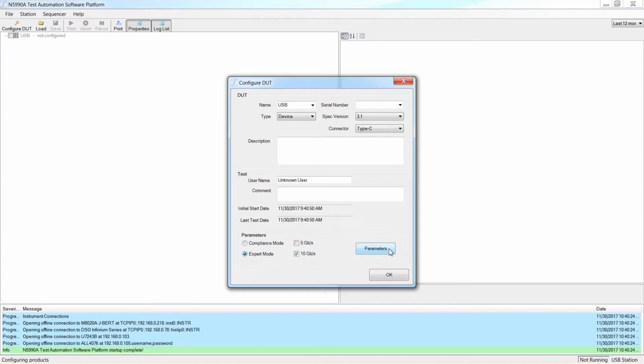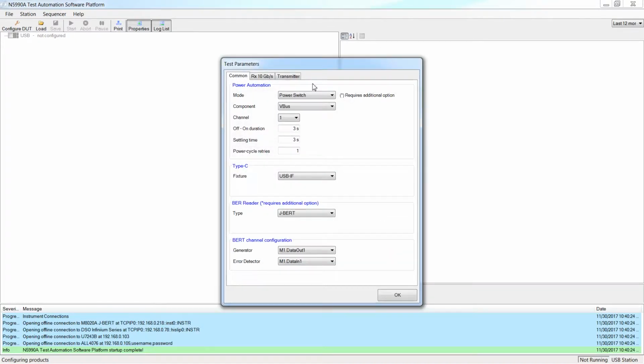We click on Parameters. In the Common tab, we can configure the power automation options. If you remember tutorial part 1 about the station configuration, we selected a power switch to automate the DUT power cycling, which requires N5990A option 008 remote power management support. Since we are testing a bus-powered device, the power will be supplied at VBus. If we tested a device that requires an external power supply, we would have to select main power. We can select which power switch channel to use. The available options depend on the model selected.